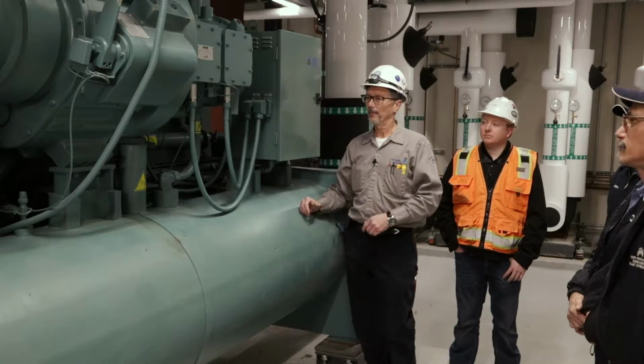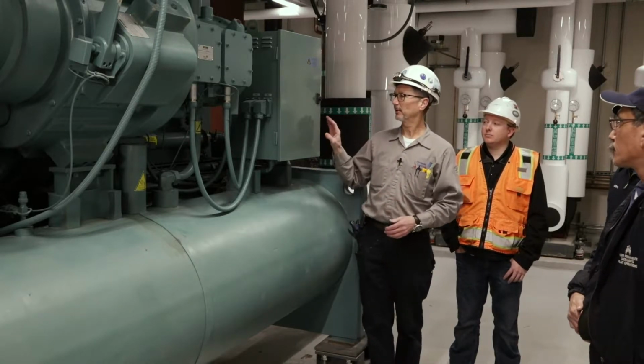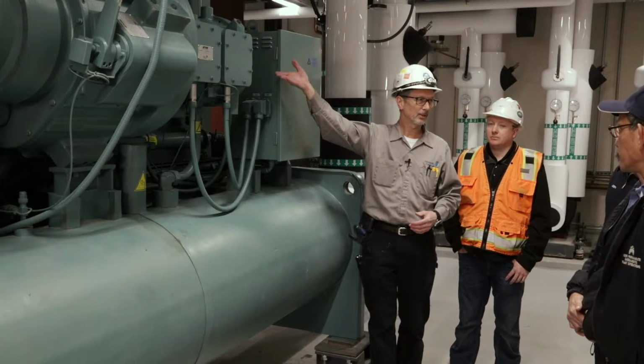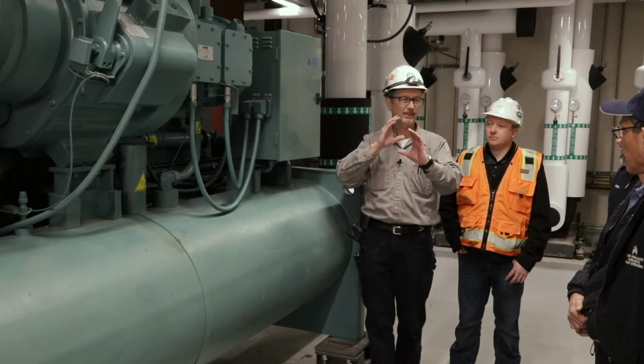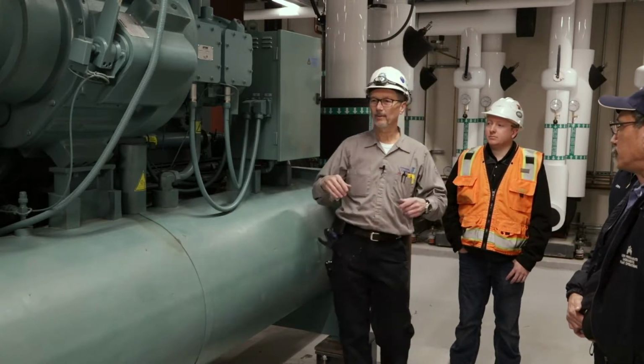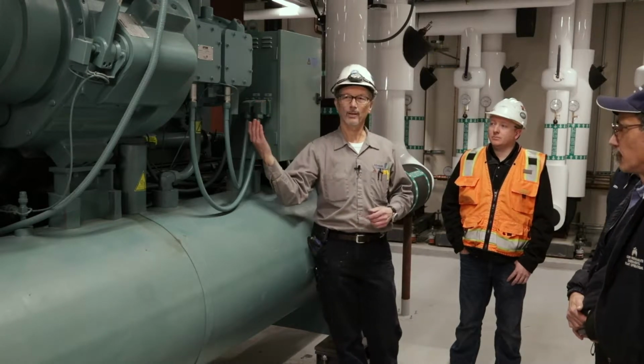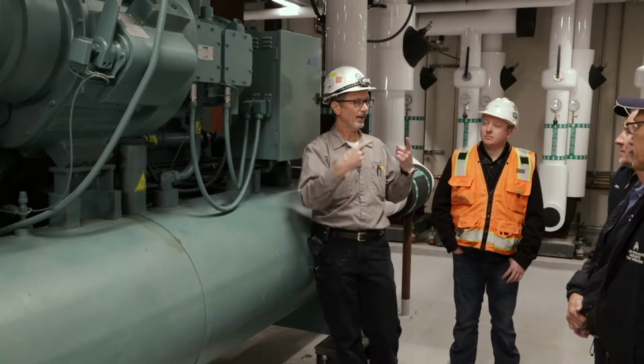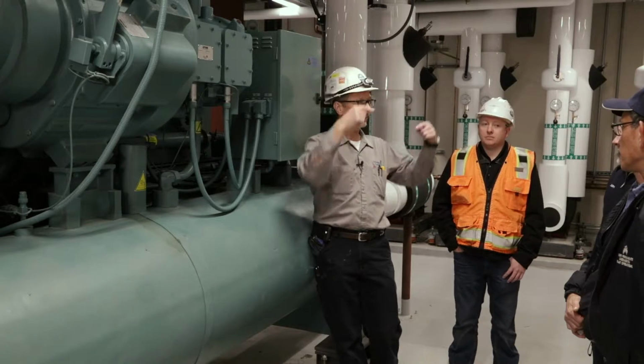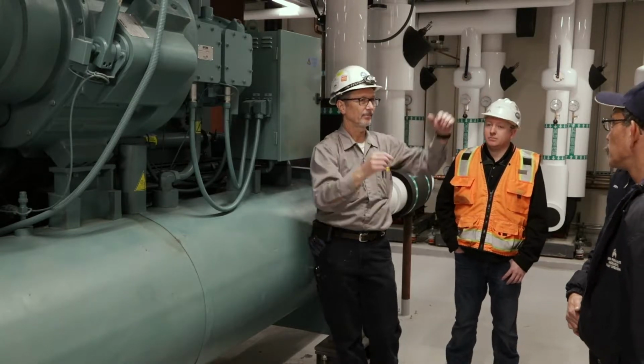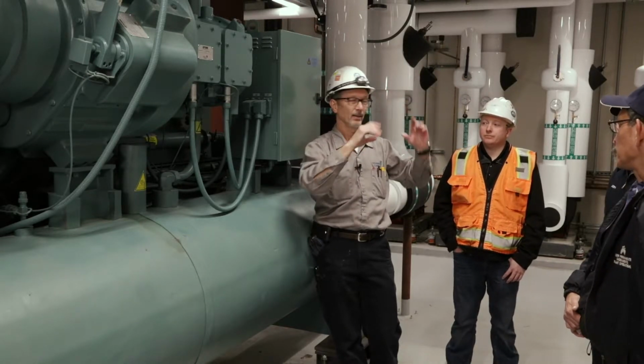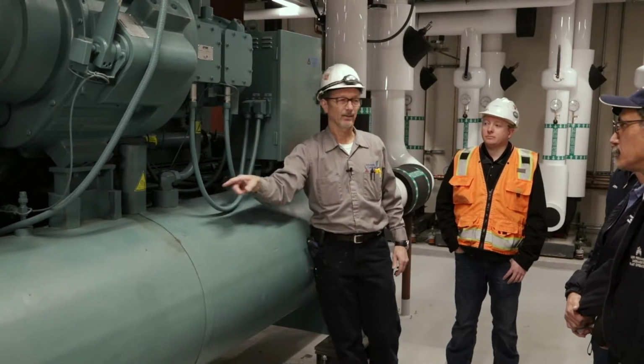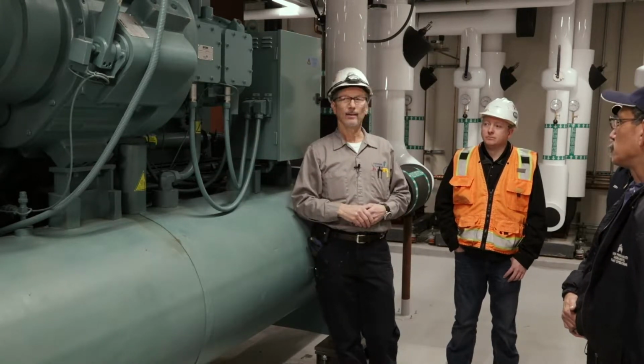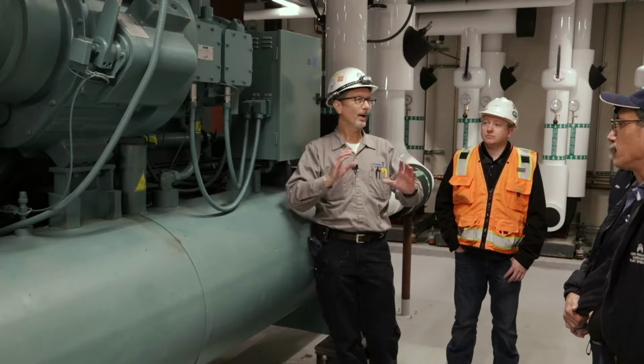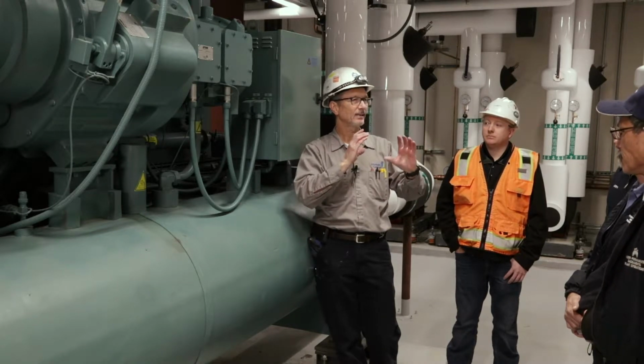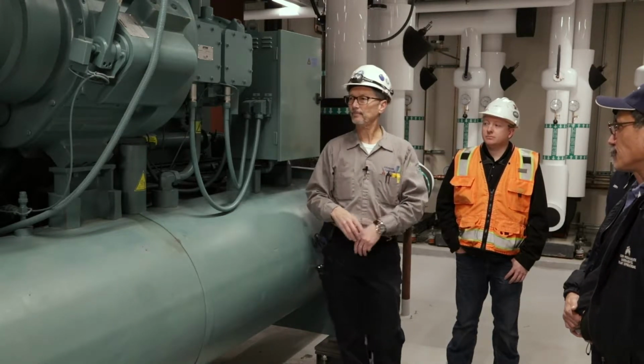So the first thing that happens when you start the chiller is it levitates the bearing, brings it up and maintains its position. And it does that with 4 magnets on one end, 4 magnets on the other, and they're at opposite sides at either end, and so that maintains a position. There are sensors that look at that all the time and measure where it is in its space and just maintain its position all the time.